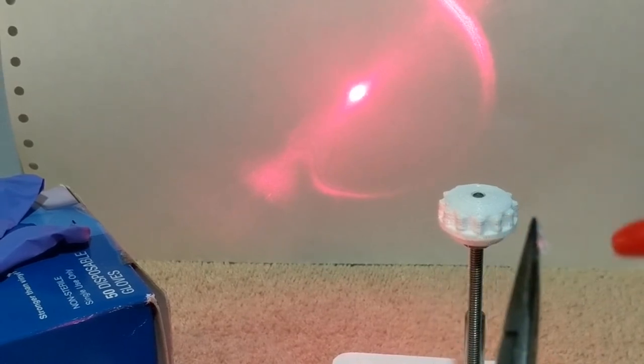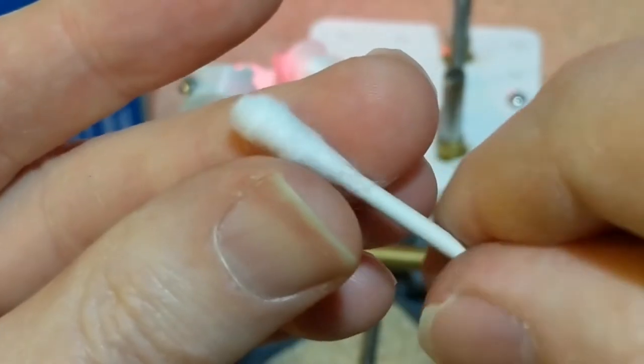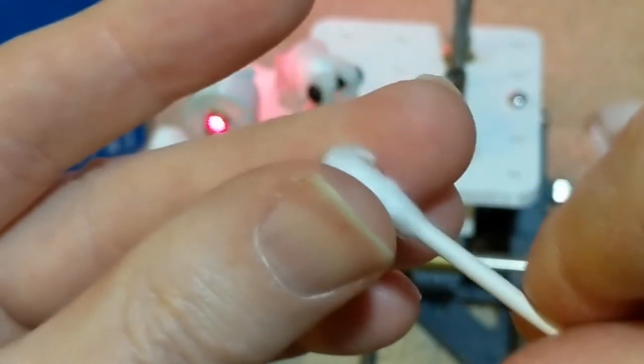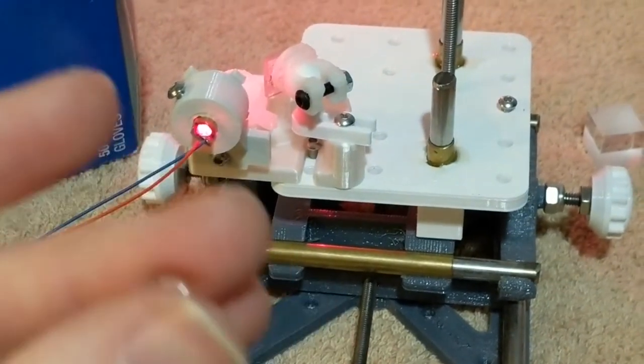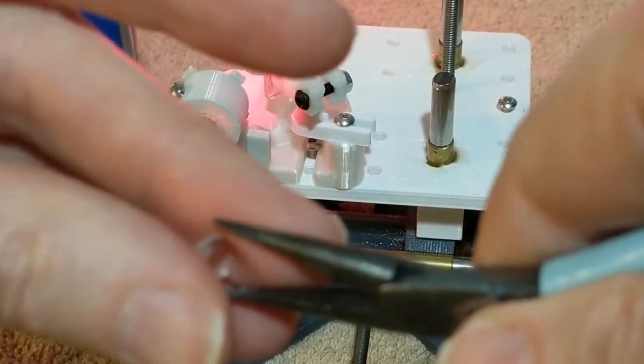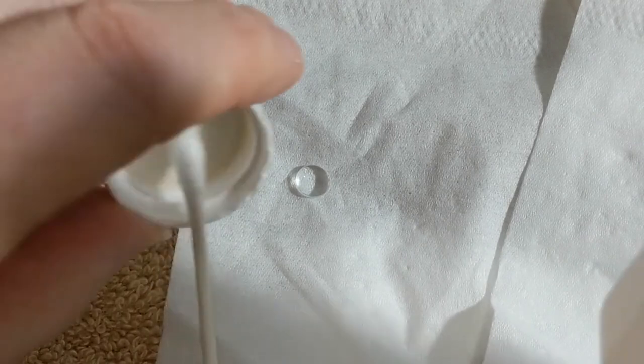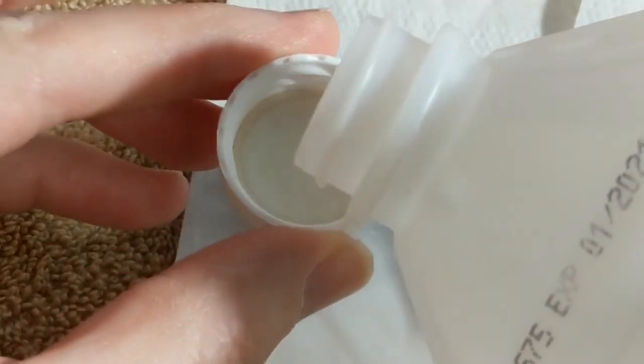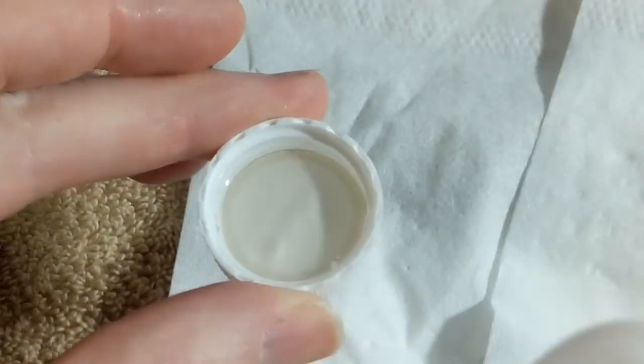Don't touch it with your finger but with the q-tip should be fine. Then pull the sides apart carefully and it slides in. Sometimes I have to push it in while spreading the holder. Look straight in and make sure it isn't crooked. I usually push it gently with my finger now and sometimes it wiggles a little which is fine. Sometimes it takes two or three tries. Let's test it. Looks great. Looks really great. So that was typical. It took three tries to clean this lens. Again, try and use just air puffs first. Then try just a dry q-tip. Alcohol usually isn't needed unless you see grease. At the far extreme, sometimes I soak the lens in the cap of the isopropyl alcohol for five minutes before starting, but very rarely.